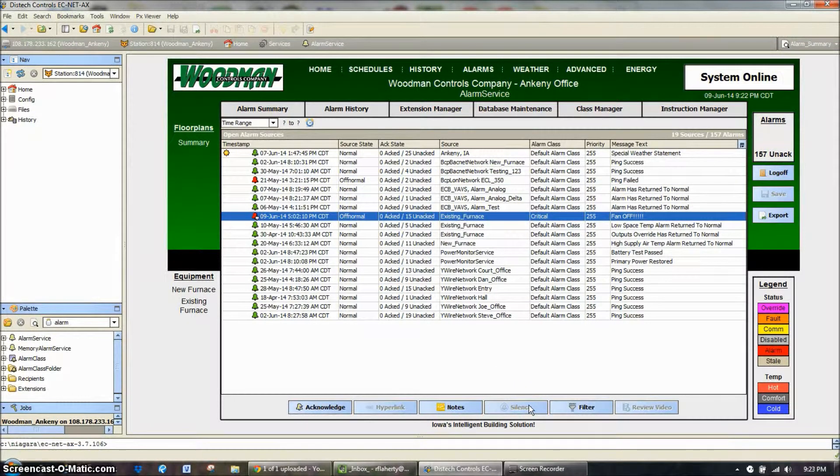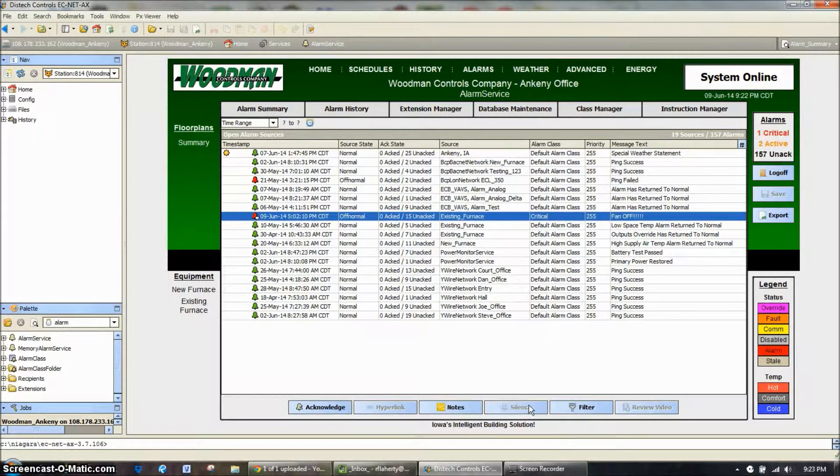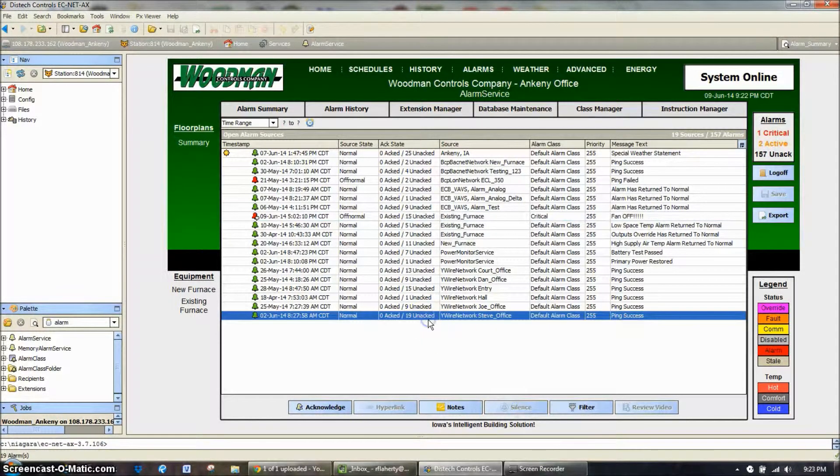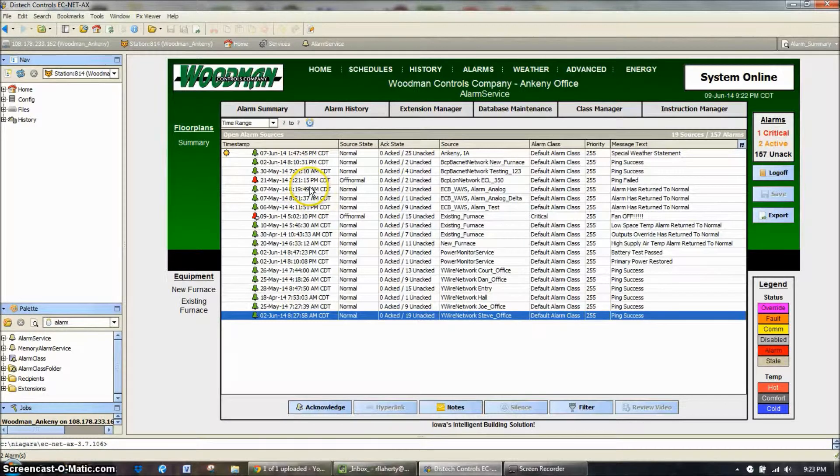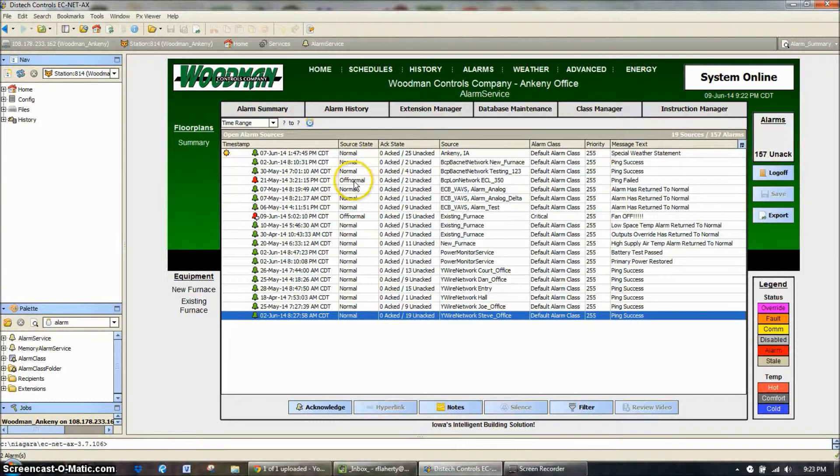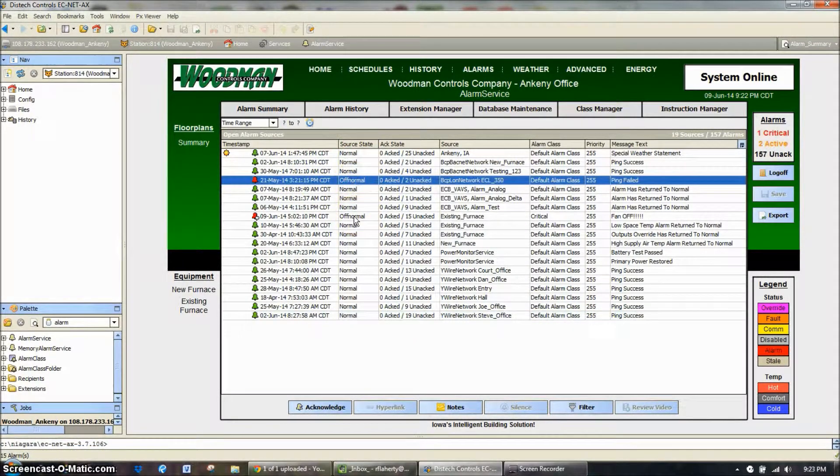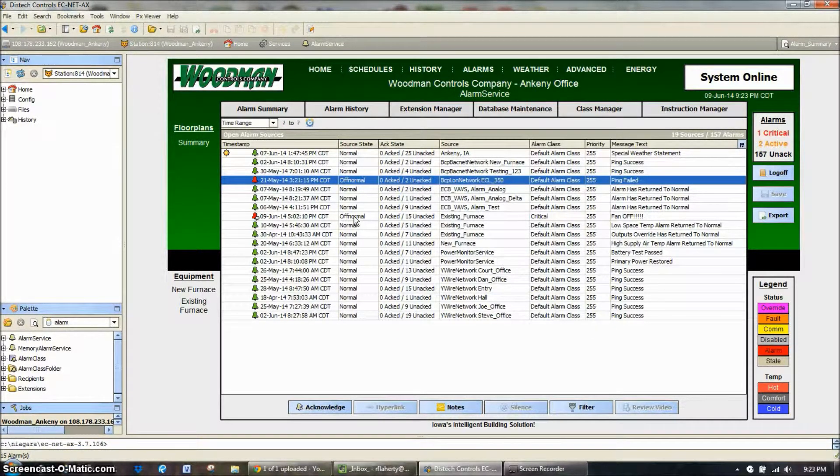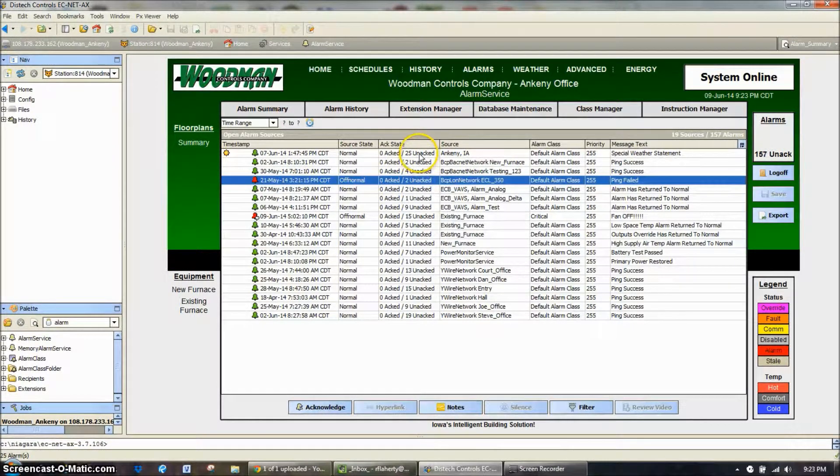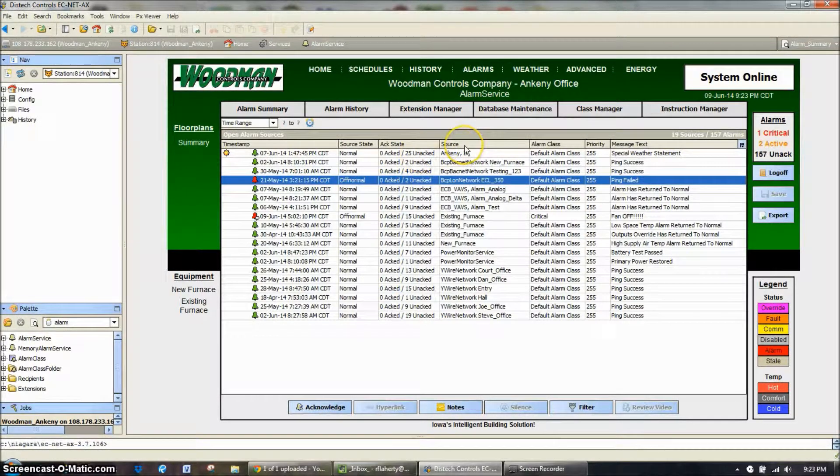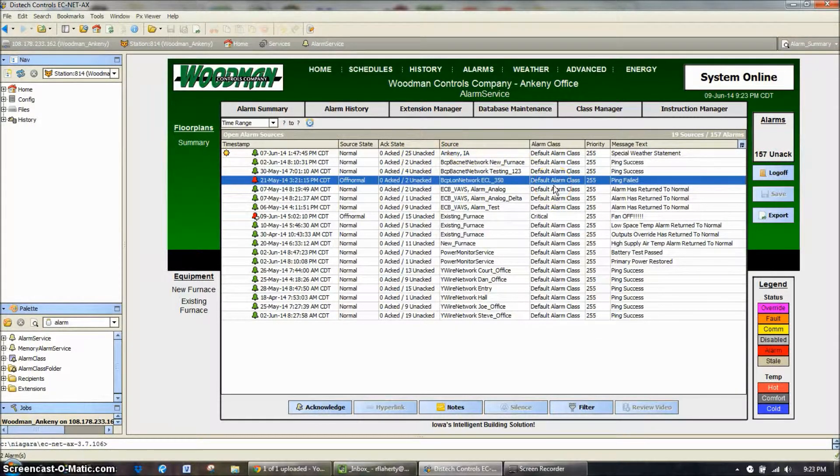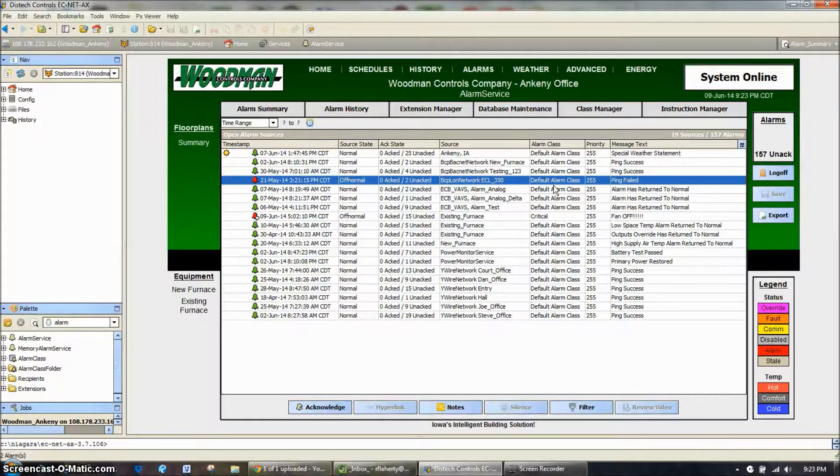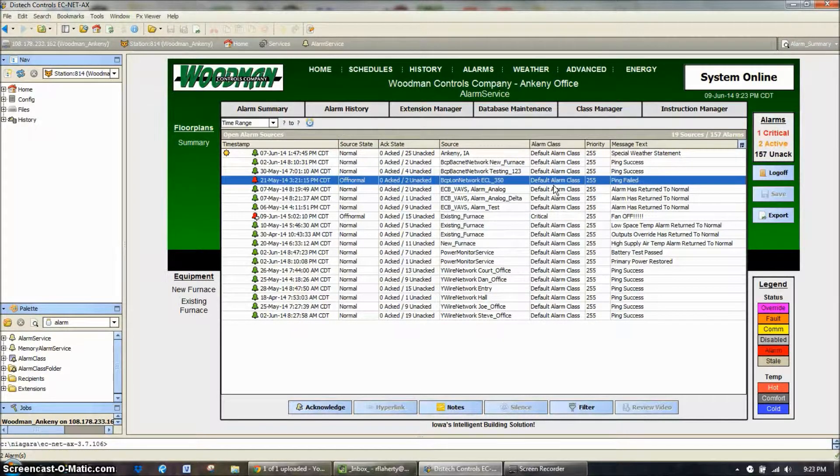So looking at this, the first thing that it shows you is the date and time that the alarm has happened, its source state, so we really only have two things that are off normal right now. Everything else is alarms that have happened and then cleared, and then we can see whether they're acknowledged or unacknowledged. The source, the alarm class. The alarm class is, since it's a default alarm, it's not an emergency. It's just something, an event that happened that we wanted to keep track of.